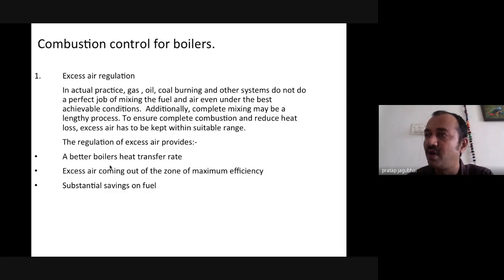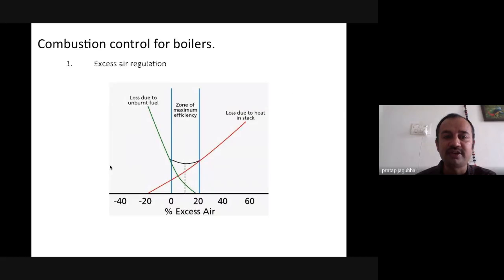Otherwise, if we give more excess air, it means we are losing heat. This heat escapes from the chimney as more fuel is burned. So what to do for that? We need to keep the excess air near 10 to 25% in the case of an oil and gas fired boiler, and 30 to 50% in the case of a solid fuel boiler. If we always provide this efficient band, and if we have tighter control, we will have the highest efficiency and highest control possible for the boiler.